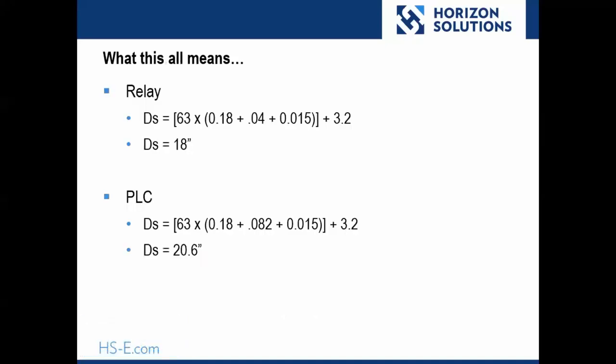What this all really means is that with the relay solution, you could mount the light curtain 18 inches from the hazard. With the PLC, the hazard would have to be more than 20 and a half inches away from the light curtain.